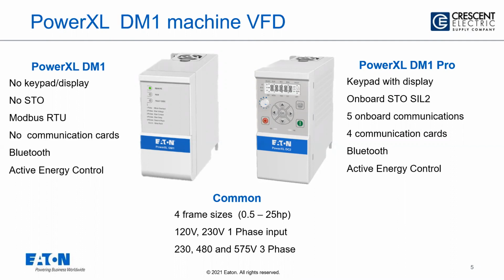So this DM1 series has 4 frame sizes that goes up to 25 horsepower. It's a constant torque rated drive. So that's 25 horsepower constant torque, so your conveyor belts and augers and things like that, which will do a 30 horsepower variable torque pump or fan. And we have this in a 120 volt and a 230 volt single phase. So it allows you to come in with a single phase voltage and then go out with a 3-phase. And we also have your standard, which is your 230, your 480, and your 575, 3 in, 3 out. So a wide range of voltages, a wide range of horsepowers, and really just chock full, way too many features for me to talk about on one slide.